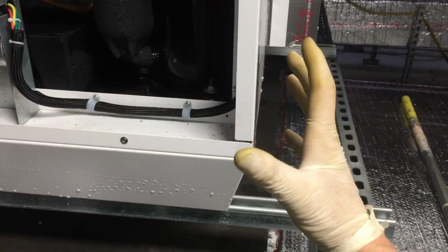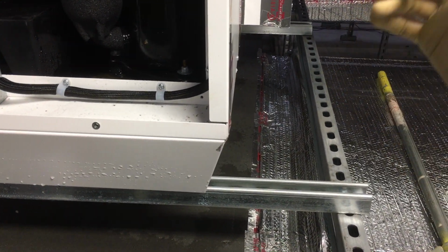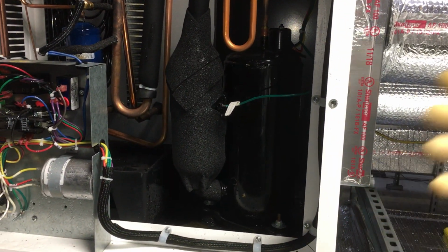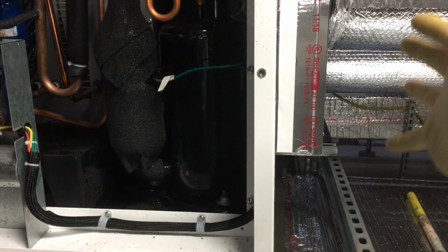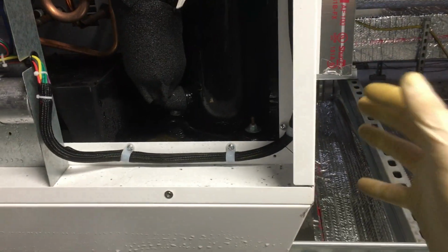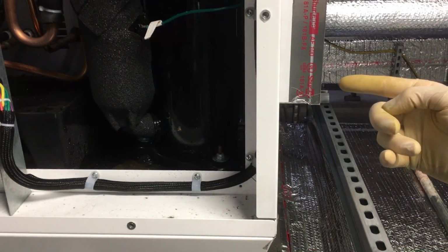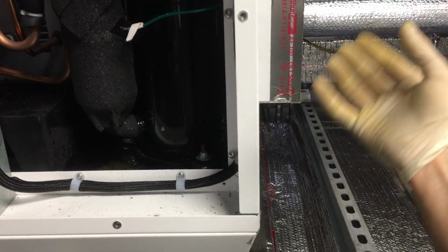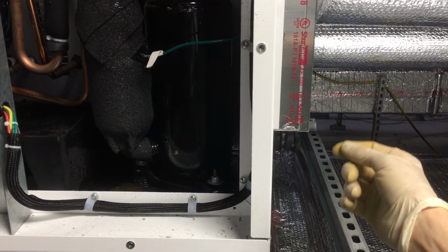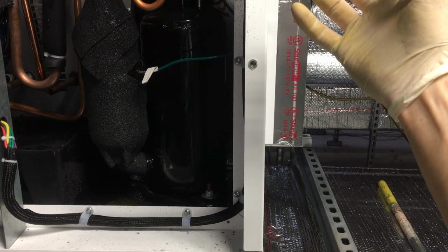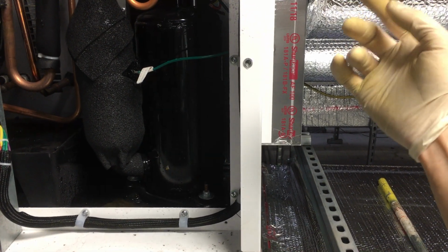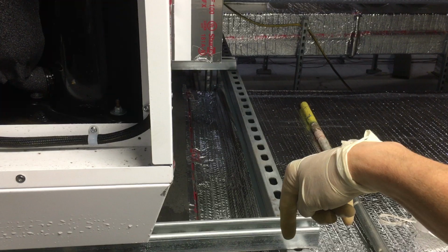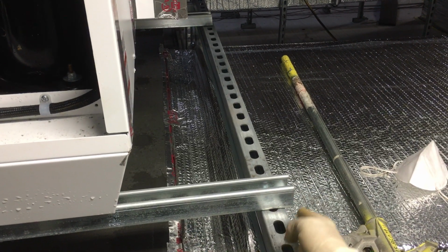Now you have this system on several different rooms, and you have a processing plant that has 3 shifts running 24/7. So you always have some rooms on the system that are doing cooling, making waste hot energy, hot water. And so that would normally be thrown away, money from PG&E spent, thrown away to the atmosphere, but instead you shift it over to this room in the form of water that is heated, and just run it through a coil and you reheat.